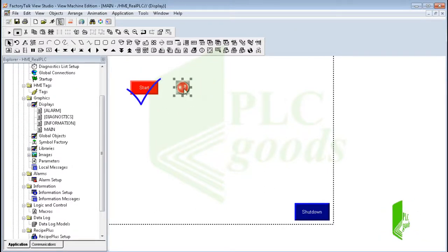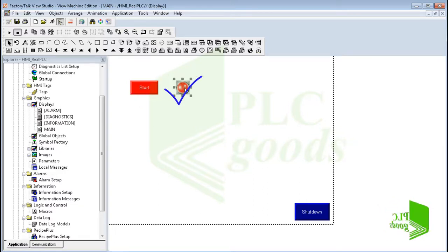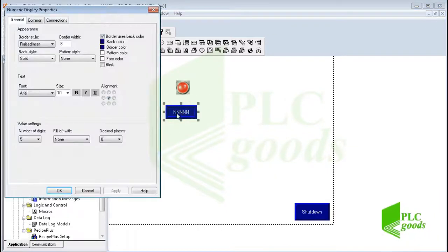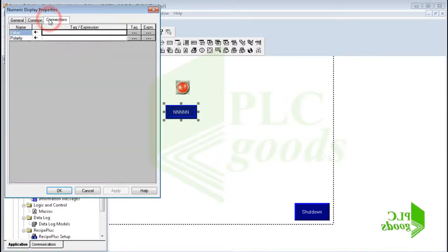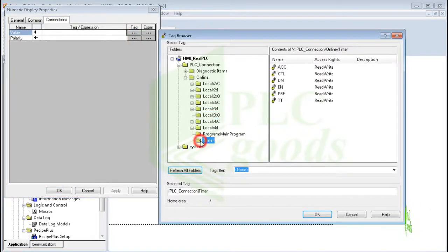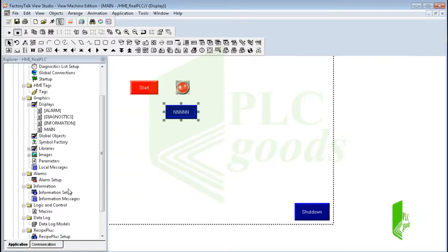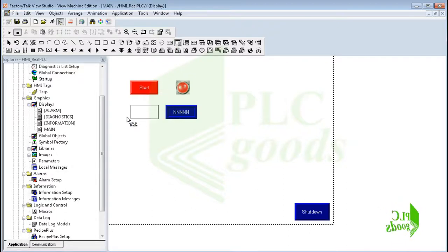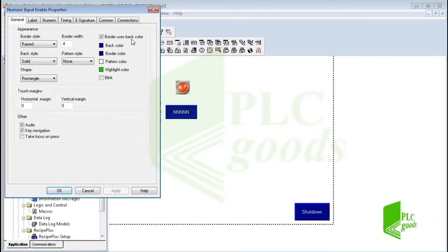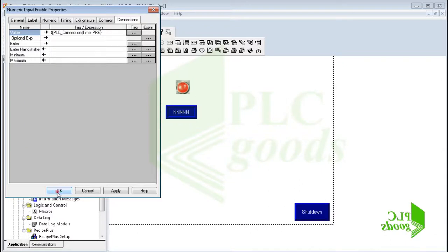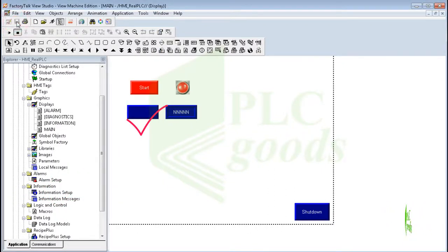Until now we have seen how a boolean tag can be changed by an HMI screen or its state displayed. Another data type is integer numbers. Let me insert a numeric display into my screen and connect it to the accumulator value of the timer inside the PLC program, so it will display the timer time in milliseconds. Also, I can change numeric data from the HMI screen using a numeric input enable object, which I'll connect to the preset value of the timer, so I will be able to change the preset timer value.